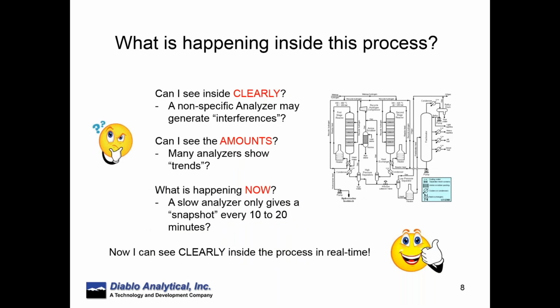So if we step back again and look at our process, the question is, can I see clearly? Usually, when you're picking an analyzer, you want to pick one that is specific for the analytes in question. In other words, you don't want interferences to cause problems with actually seeing your components of interest. So that's the first question. Have I chosen an analyzer that really can see the components I want to see? And the next big question that comes along, and often is not able to be achieved, is, can I see the amounts? In other words, is it a quantitative analyzer, or does it just monitor trends? And then finally is the question of real time, or what is happening now, and how can I see quickly what's going on?